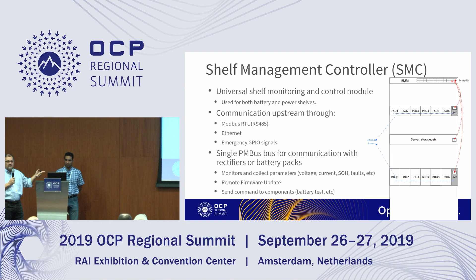With respect to the SMC controller, that is the element that marries the power system to the facility communication or control fabric for this particular rack. More than one way to do that. We're allowing for an RS-485, we're allowing for Ethernet, depending on what you need. We're hoping to make this very flexible, and as Hamid said, PMBus, but from that SMC to the power supplies, you'll be able to read telemetry, PSU health, power consumption, all those sorts of things, as well as upgrade, downgrade firmware, and do all battery test commands. It's the same SMC controller for the battery shelf also.